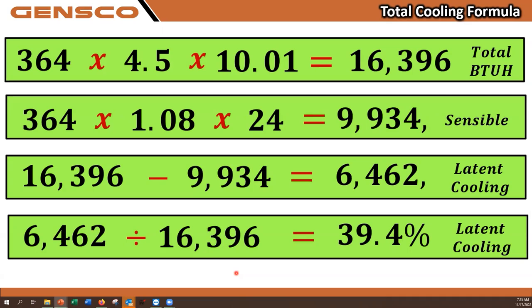Now, if you actually come out with a number like that, that's high. All these units have ratings to do latent cooling somewhere in the 20 to 25% range. So when I actually do one and see a number like this, I know my humidity is a little high in this space. This could be for many reasons and probably something we could cover in a future quick hitter. But this would alarm me if my actual latent cooling was that high.